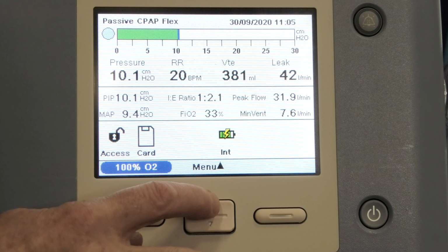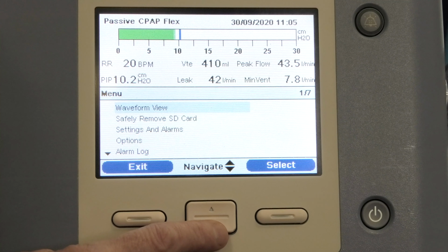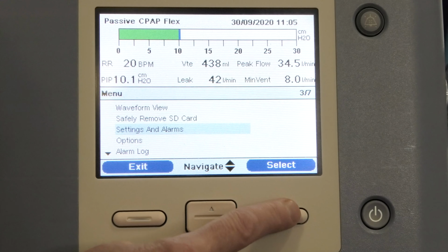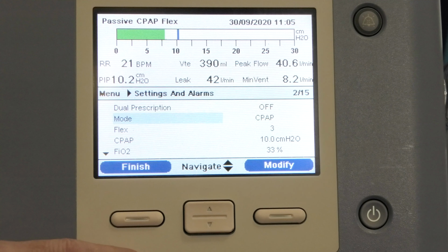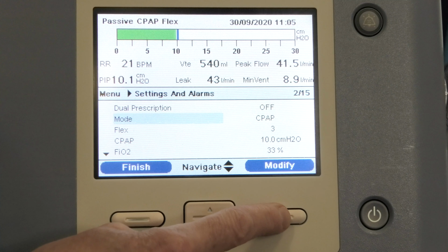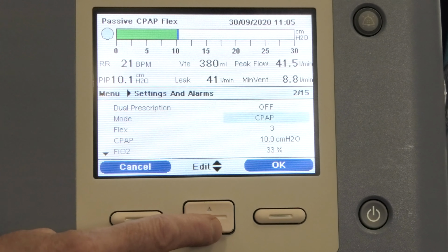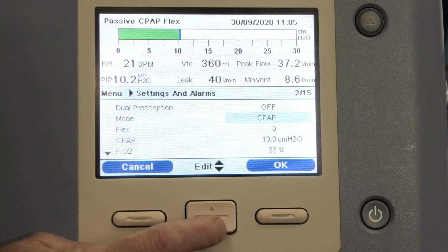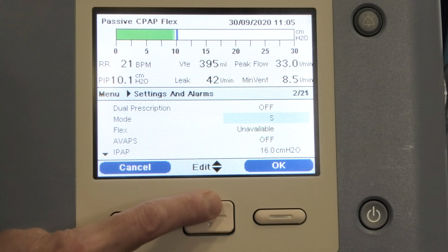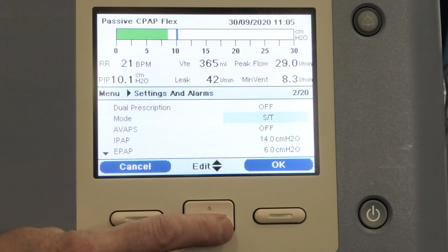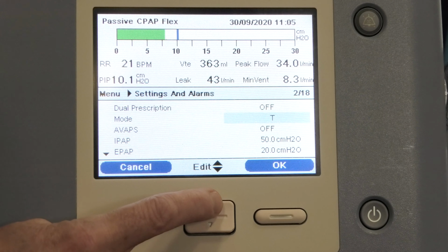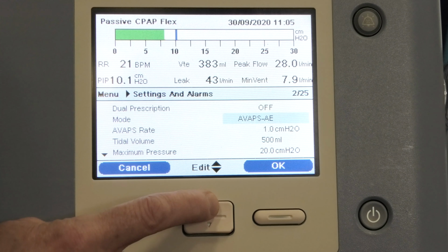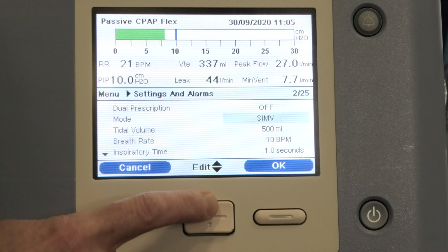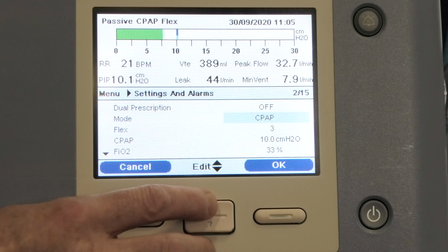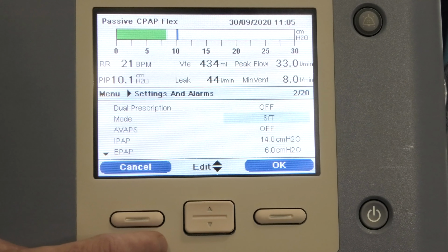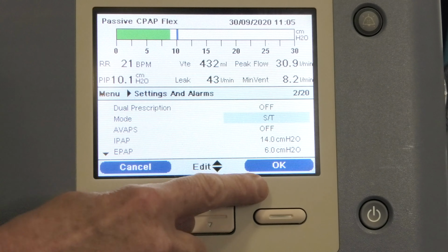Again, we go into our menu, scroll down to settings and alarms, press select. This time we go to mode and press modify. Now there are lots and lots of different modes on this ventilator. I can tell you that 2 down or 2 up is ST, spontaneous timed, which is BiPAP. There's timed, which is full ventilation, pressure control ventilation, AVAPS, pressure control SIMV. There are many different settings, but all we're going to use this ventilator for non-invasively is CPAP or ST. ST is bi-level non-invasive ventilation. We're going to press OK.